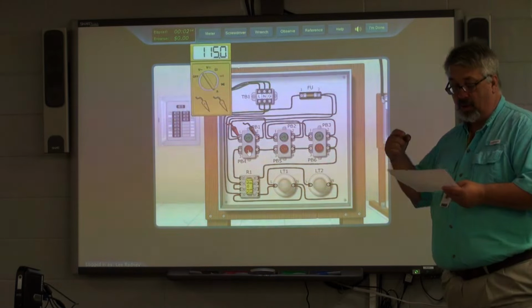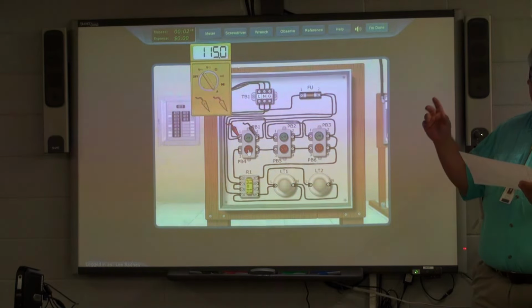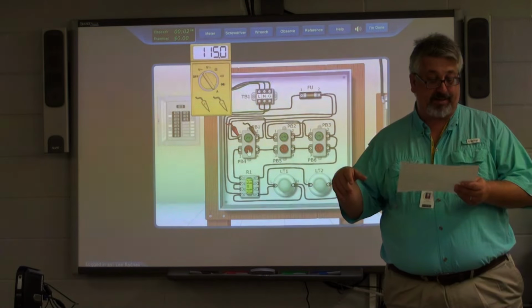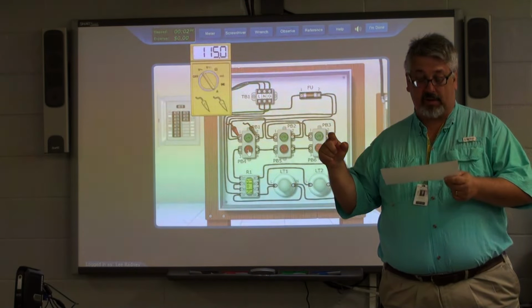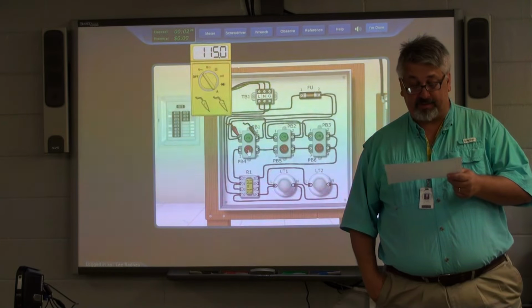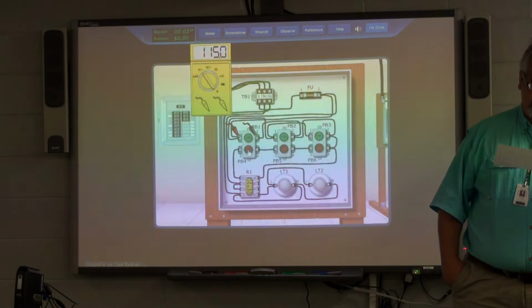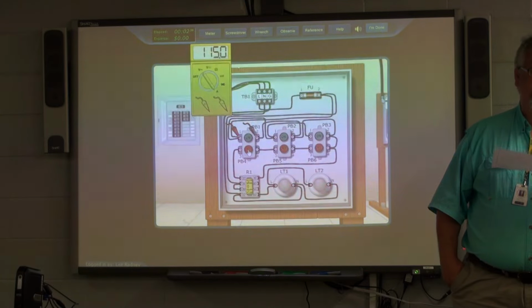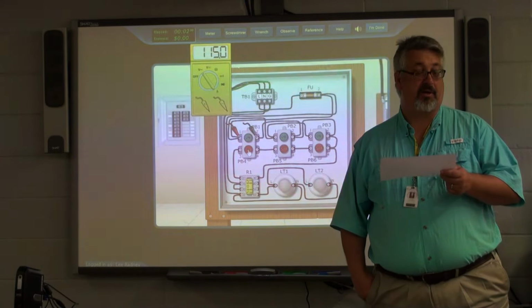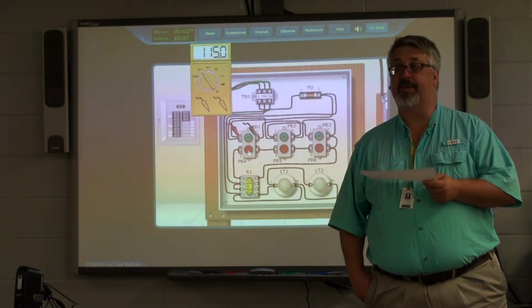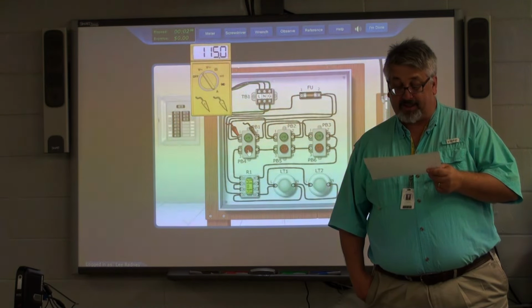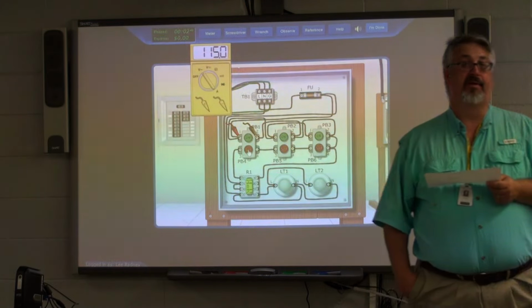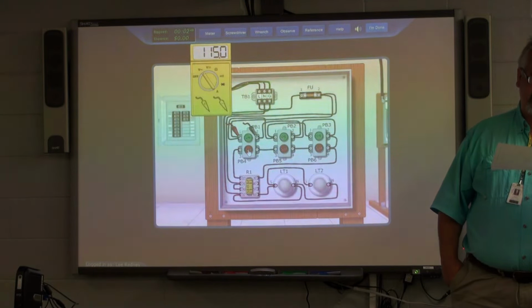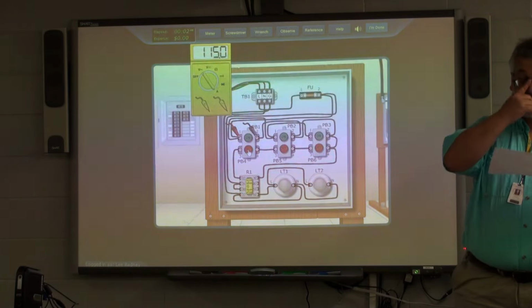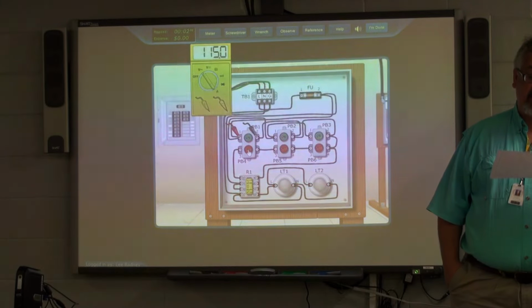Now, what we're saying is happening is as soon as we press one of those buttons, we're engaging the coil of that relay. If you look on your connection wiring diagram, you see what I was talking about: pins 2 and 7 are the coil. Take a look, you see the little circle that represents the coil going to pins 2 and 7. Pins 1 and 8 are the commons for the contacts. We've got two sets of contacts: one with pin 1 that feeds the normally open and normally closed 3 and 4, and pin 8 which feeds 5 and 6.